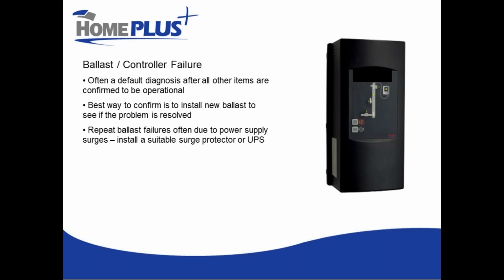The one thing that I would suggest to always check before you assume a ballast failure, even if the controller is indicating such, is to make sure whatever safety harness or reed switch type of apparatus is on that unit is connected properly before assuming that it's a controller, because I have seen cases where it indicates a controller failure, but really it's a connection failure.